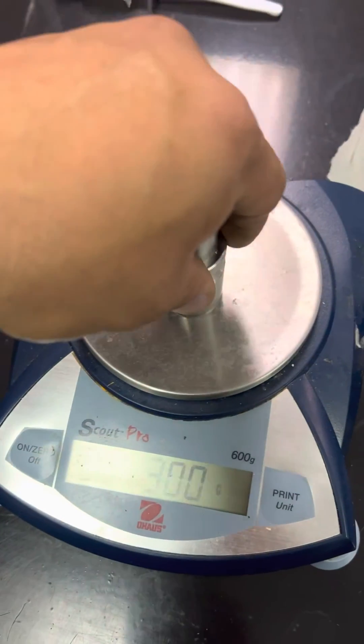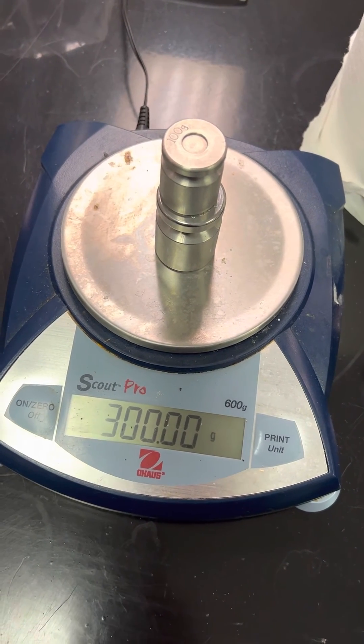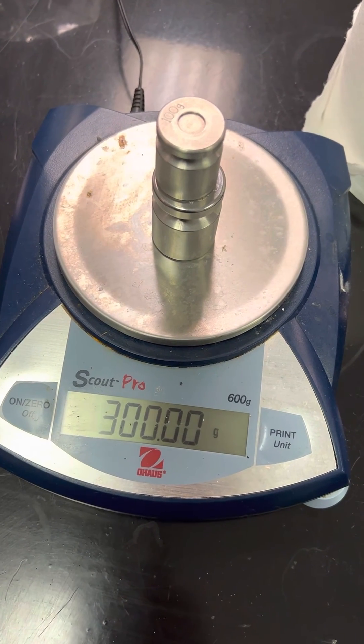It asks for a weight. Give it a couple of seconds to stabilize, and then you press the same zero key. And that's pretty much how you adjust the calibration on an OHAUS SP or Scout Pro.